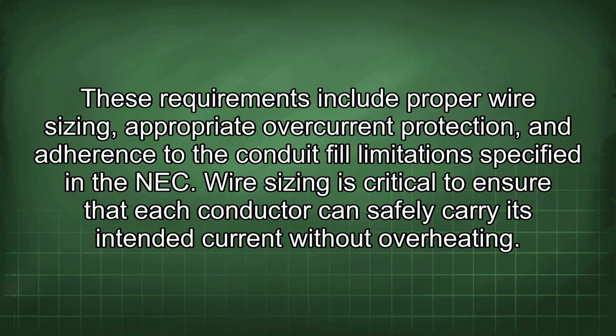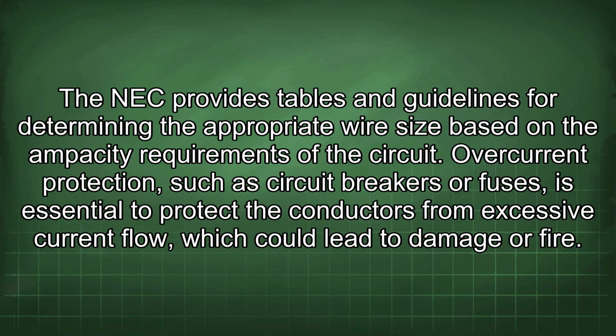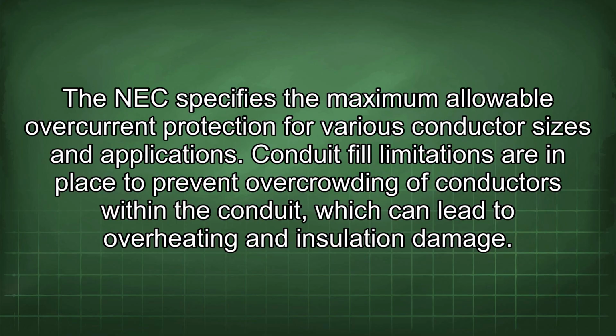Wire sizing is critical to ensure that each conductor can safely carry its intended current without overheating. The NEC provides tables and guidelines for determining the appropriate wire size based on the ampacity requirements of the circuit. Overcurrent protection, such as circuit breakers or fuses, is essential to protect the conductors from excessive current flow, which could lead to damage or fire. The NEC specifies the maximum allowable overcurrent protection for various conductor sizes and applications.